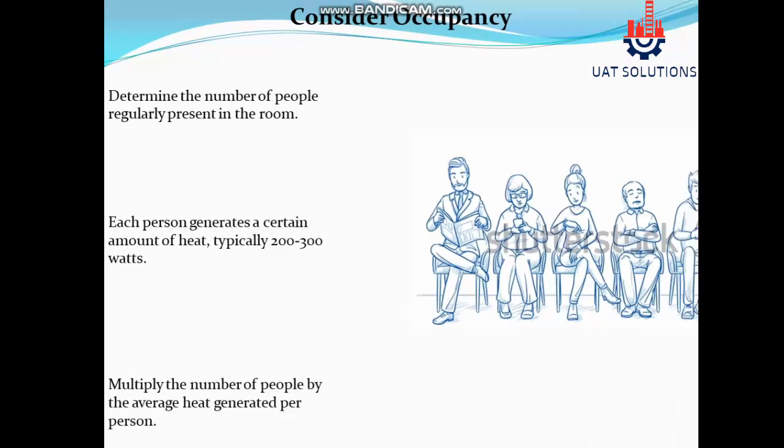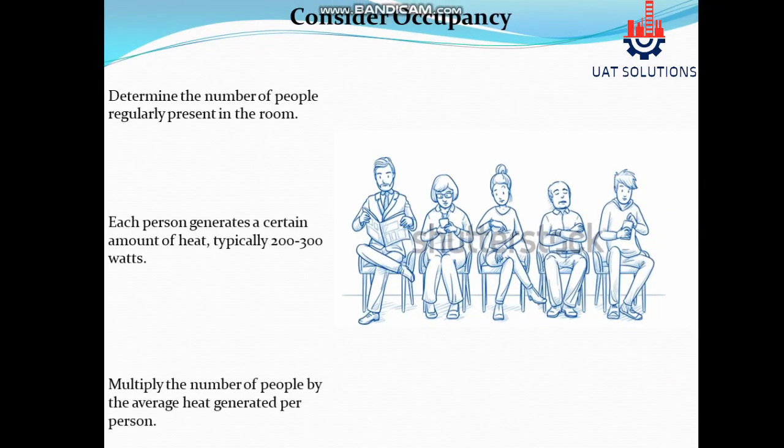Consider occupancy: determine the number of people regularly present in the room. Each person generates a certain amount of heat, typically 200 to 300 watts. Multiply the number of people by the average heat generated per person to get the total occupancy heat load.